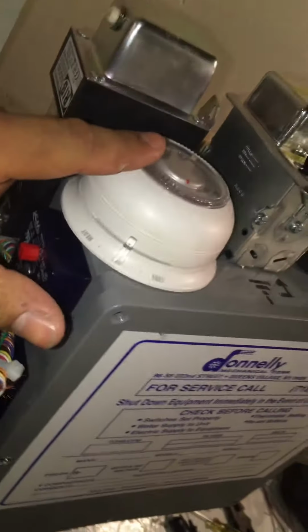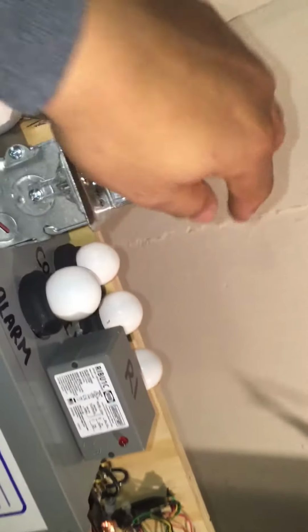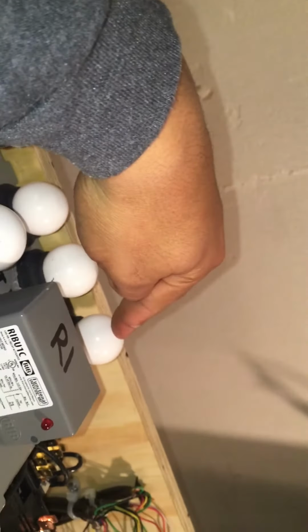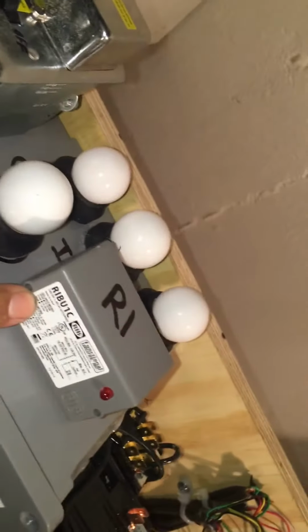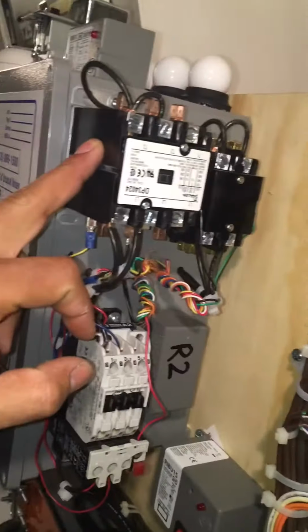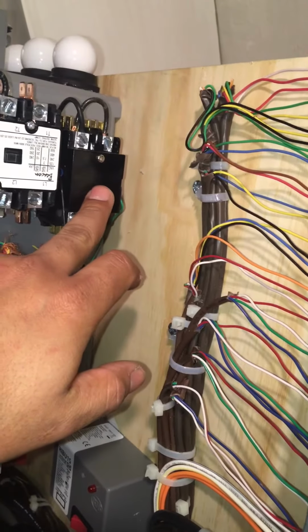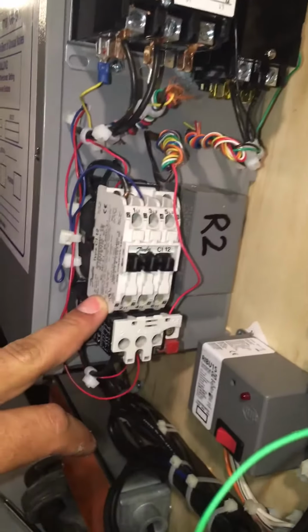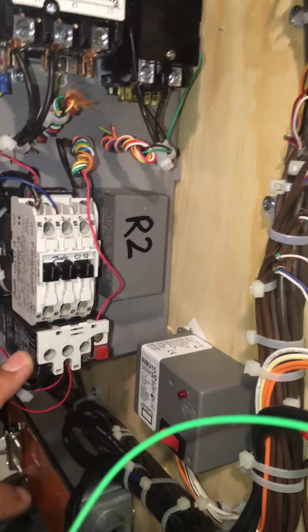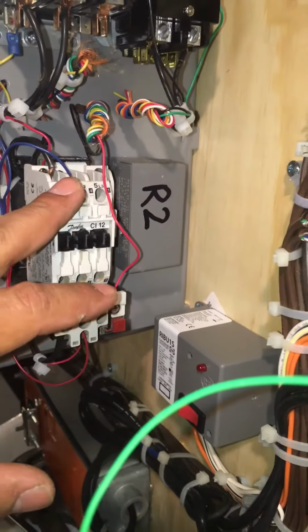We have a typical yo-yo stat, 50 VA transformer, disconnect with circuit breaker. This guy is our fan, this is our compressor, and this is our pump light, this is our alarm light. It's an interlocking relay labeled as R1. And on this side we have the compressor contactor, the fan contactor, and the condenser water pump contactor with overload relay feature. And we have the L2 used as the auxiliary contacts of the switch.